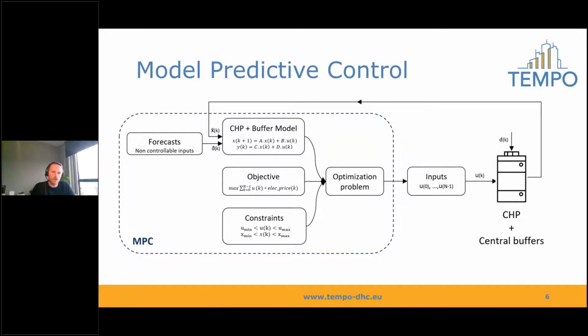We can recalculate this plan multiple times a day. At the moment, we recalculate the plan twice a day, once in the morning and once in the evening. This is then mailed to the network owner, and he puts it into the system so that the CHP will follow this plan. The main advantage of being able to replan during the day is that our forecasts of the total heat load and of the heat input from the waste heat side are always off. They are never 100% accurate. So every time we recalculate, we start again from the real system state. And in a later stage, we will be able to send our control plan directly to an API of the aggregator, so that we don't have to get the network owner involved anymore. So everything will run automatically.